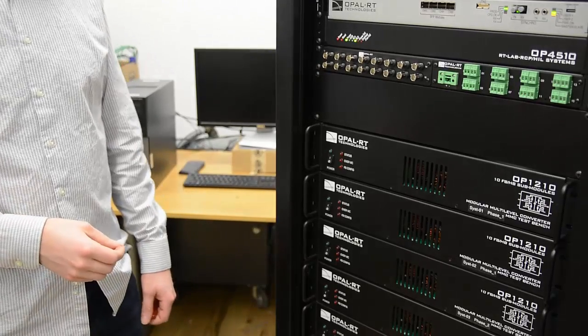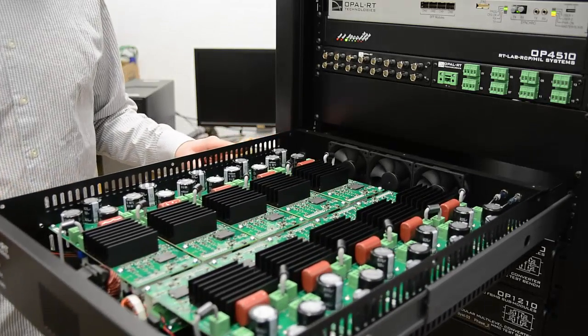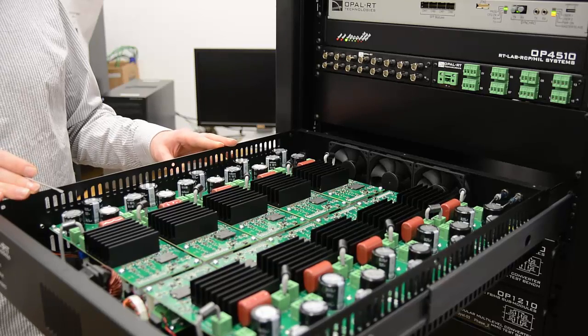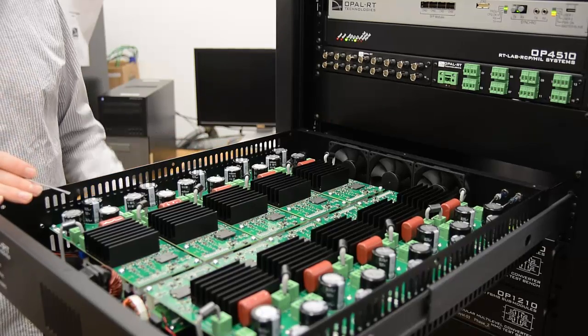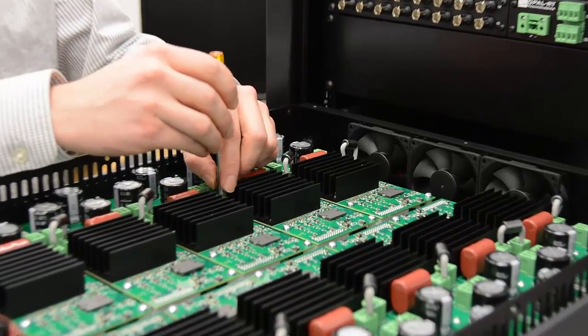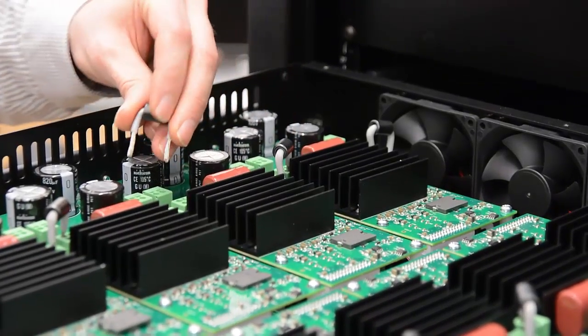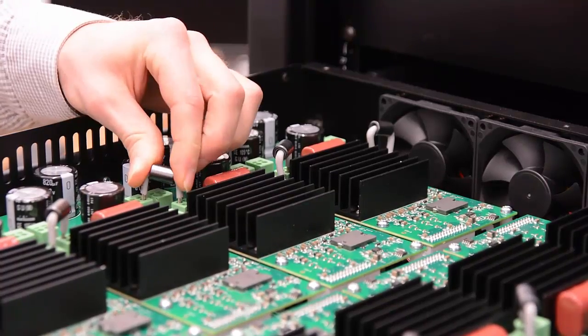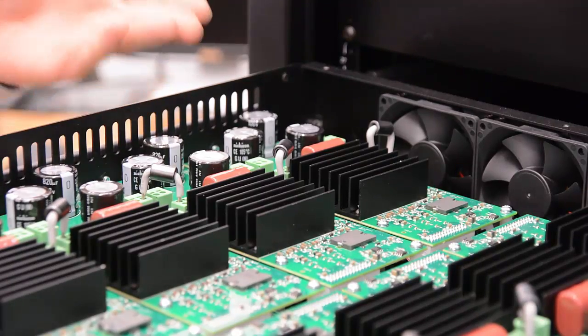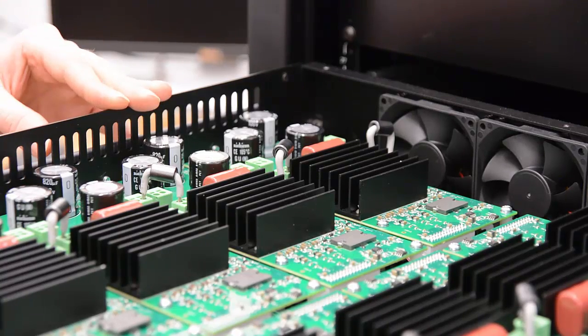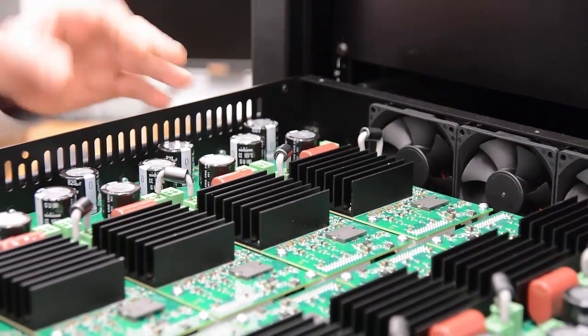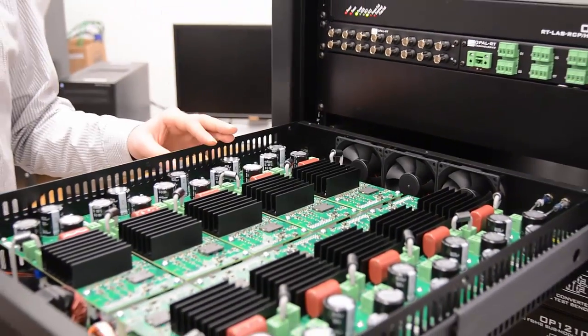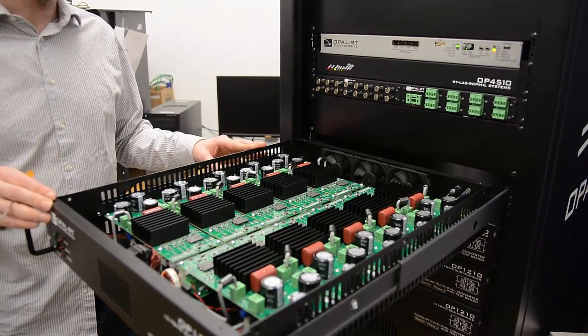Now let's take a look inside the OP1210 modules to see how the cells are interconnected. What's interesting is how easy it is to reconfigure your rack from full bridge to hardware half bridge configuration. You just exchange this jumper here that can be easily disconnected with a flathead screwdriver and reconnect it to have your full bridge connected as a half bridge. It can also be done by software by blocking one switch, but for certain research you want a real half bridge and this enables you to do it. It's also possible to connect other types of cells if required. This unit is very versatile.